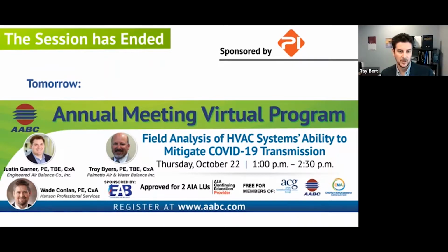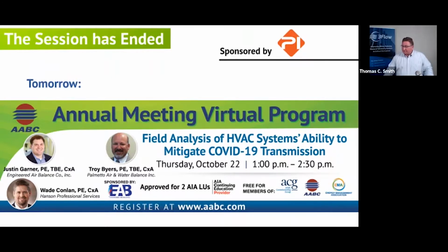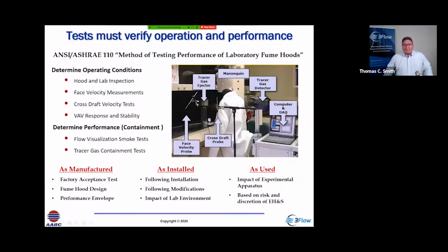So what I thought might be a decent follow-on question: where would someone start if they wanted to offer ASHRAE 110 fume hood testing services? Well, that's a really good question. And let me flip back to, okay, I'm going to show this diagram here. Well, first and foremost, if you want to do ASHRAE 110 testing, you want to offer it as a service, we've got to have all of the conditions to evaluate operational conditions. Every TAB firm is going to be able to do this. Hood and lab inspections, face velocity, cross-draft, VAV response.